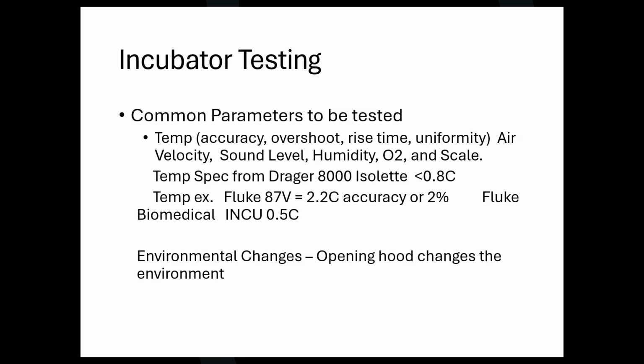Again, let's talk about the accuracy of things. I stick my 87V in there, which has an accuracy of 2.2 degrees C. The Draeger, I just looked in the manual, says you cannot have a temperature change of more than 0.8 degrees C. I know already I cannot accurately measure that if I've already got a span of 2.2 on this.